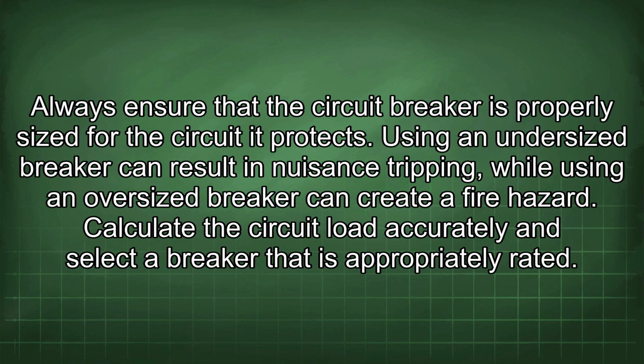Always ensure that the circuit breaker is properly sized for the circuit it protects. Using an undersized breaker can result in nuisance tripping, while using an oversized breaker can create a fire hazard. Calculate the circuit load accurately and select a breaker that is appropriately rated.